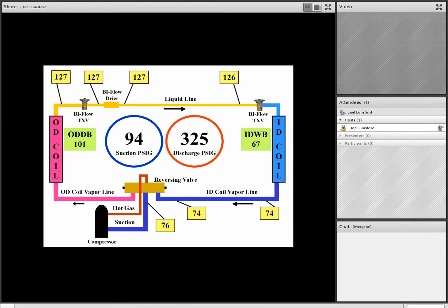So referring to your diagnosing system problems page, let's find a condition that will give us high suction pressure, high discharge or liquid pressure, about normal subcooling, and high superheat. You'll find that the answer is a high heat load on the cold coil. And that's correct. If you have a lot of heat energy hitting the indoor coil, or in this example, the cold coil, it's going to drive both pressures up, and the superheat up. But if the unit has a normal charge, the subcooling will be about normal.